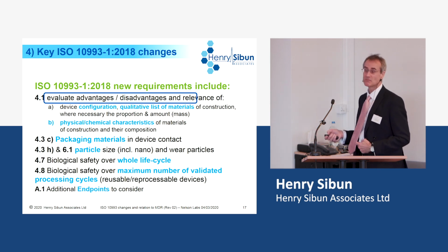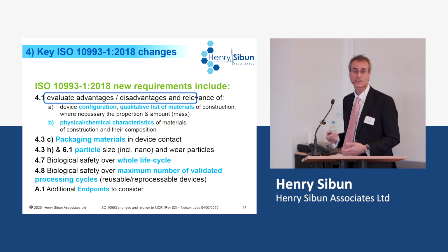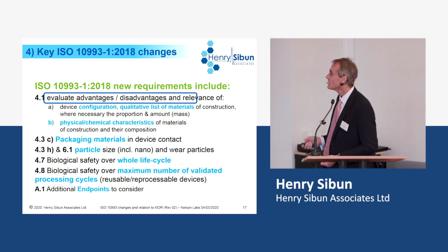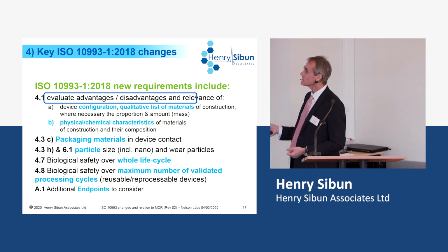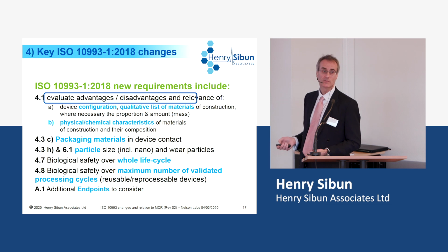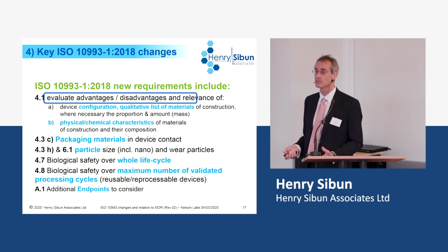It depends. On some things change, some leach very quickly. Most packaging materials that we use in devices are very well known and characterized. Particle size, we talked about, that's fairly new because it's new technology. This is important, safety of the whole life cycle. So again, during the aging of a device, when it sits on the shelf, what is the impact of that? Not just the packaging on it, but its own change.